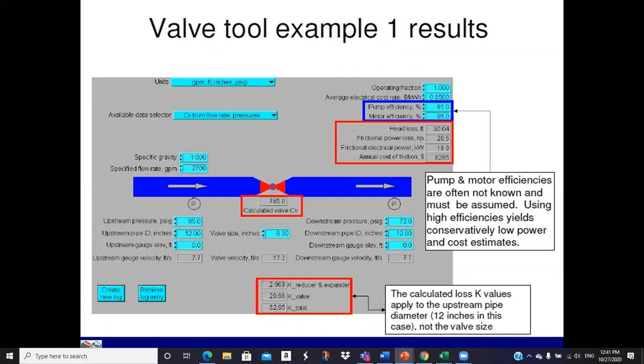We punch it in, and again, we're calculating CV from flow rate and pressure, so we put our information in. There's a note here: pump and motor efficiencies are often not known and must be assumed. Using high efficiency yields conservatively low power and cost estimates. You'd probably rather estimate it low than estimate it really high and be wrong. The calculated loss K values apply to the upstream pipe diameter, 12 inches in this case, not the valve size.